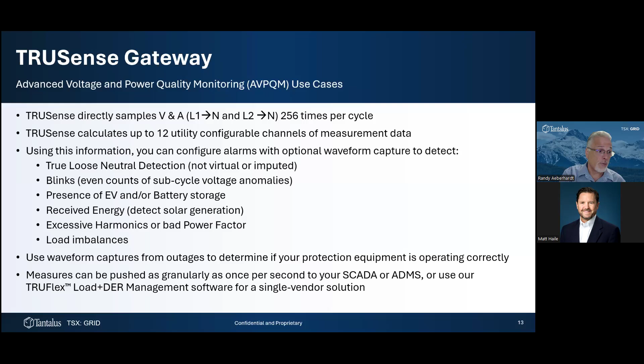Here you had a 30-second waveform capture triggered by excessive amperage. If you look at the waveform, you can see there was a lagging effect—this load, which in this case was a big fan connected to a transformer at a substation, when it turned on there was a lagging power factor. So it created some issue.